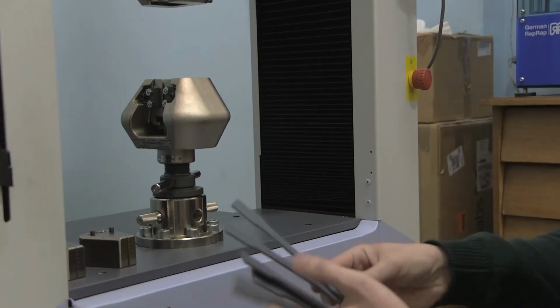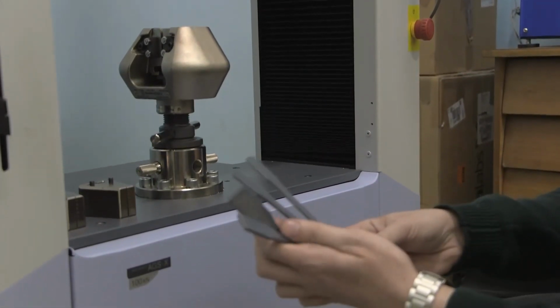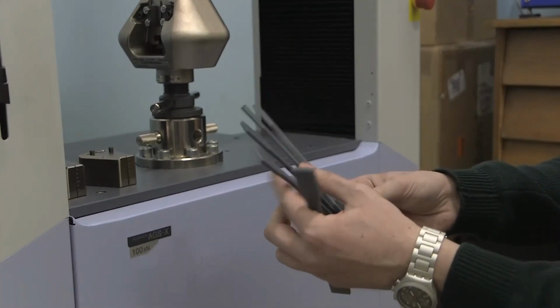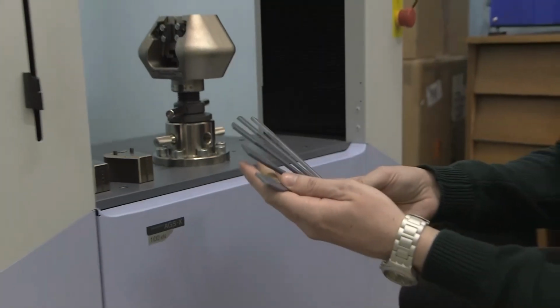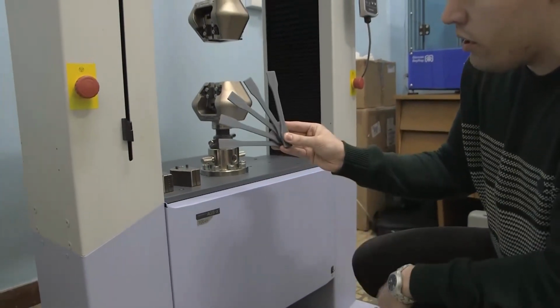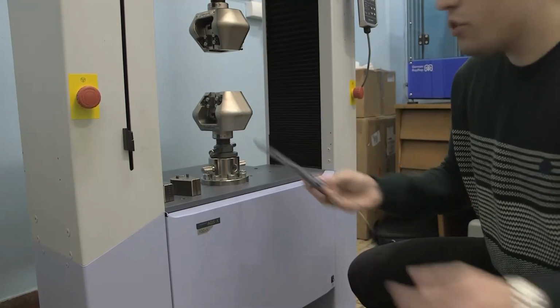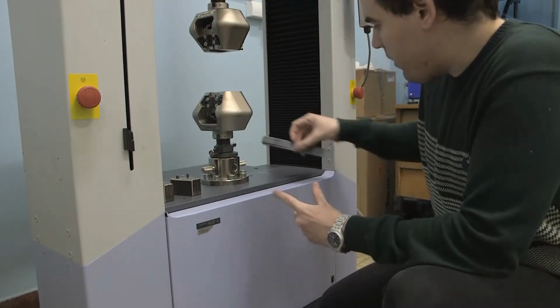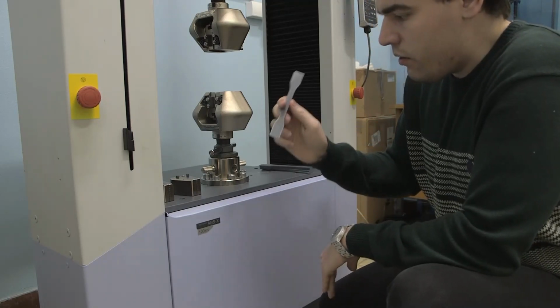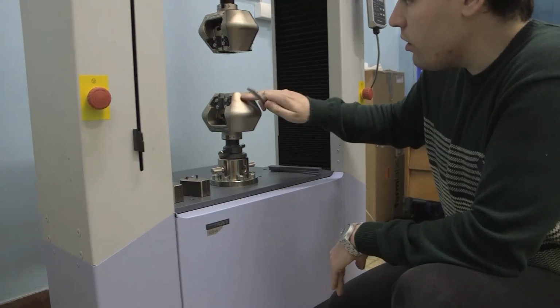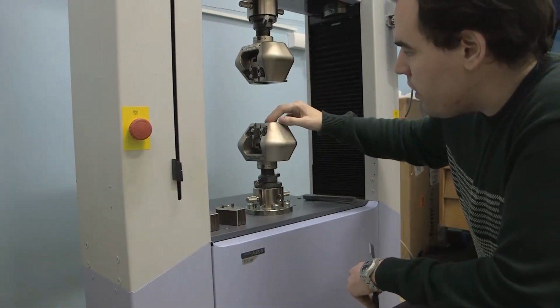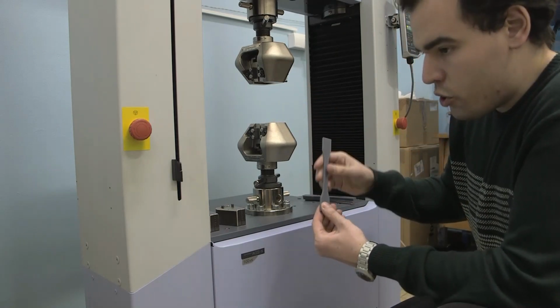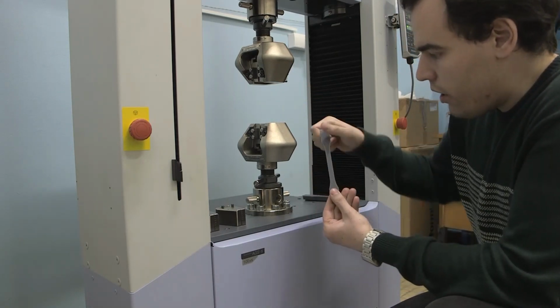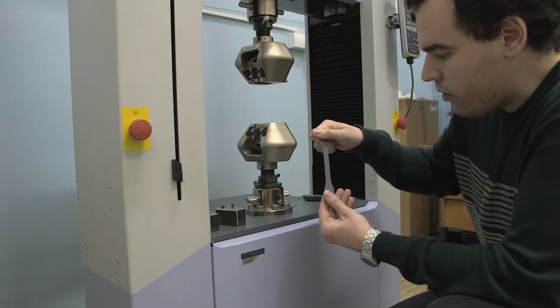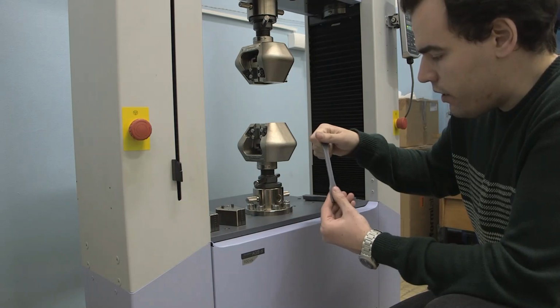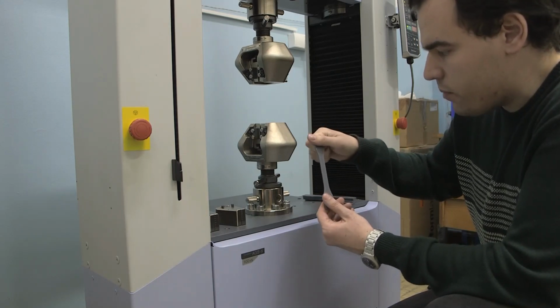All 5 are the same, and after testing 5 samples, we take an average value, and that is a value we use as a reference for the tested material. So, next thing we do is insert the first specimen into the jaws. These jaws contain plates which press the lower and upper end of a specimen, and that is how the machine holds the specimen.